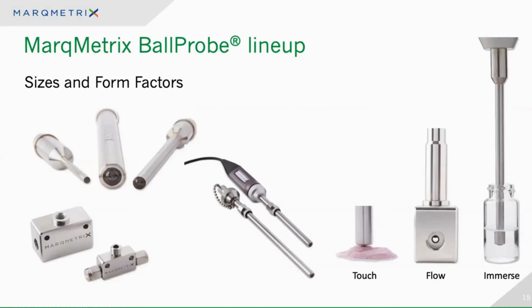Our whole thing at MarqMetrix is we can make the best instruments in the world. We can actually have the best technology in the world, but if we screw up the last millimeter, that's the interface between the hardware and the sample, you basically have a random number generator. So our primary goal is to completely reduce the challenges and the variability found in doing Raman spectroscopy due to variability in focus at that point of sampling. And we do that mainly with our Raman ball probe family of products that allow us to touch, allow us to flow, and allow us to immerse with sampling accuracy that's better than 0.1% RSD. And that's always been our goal.